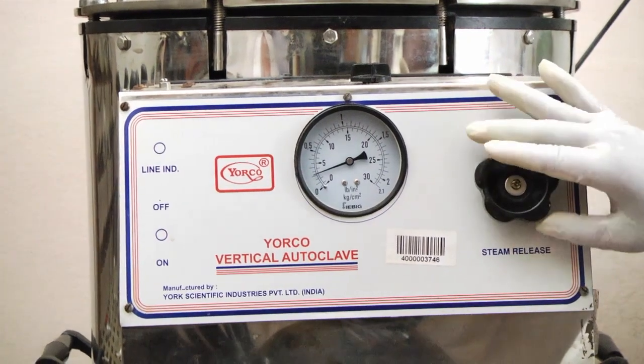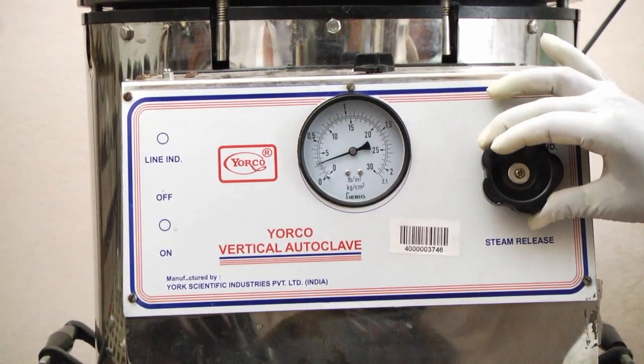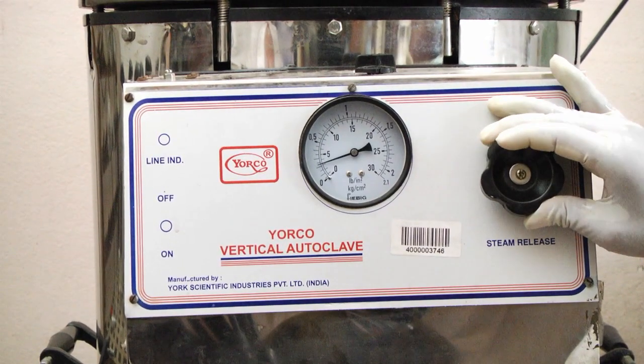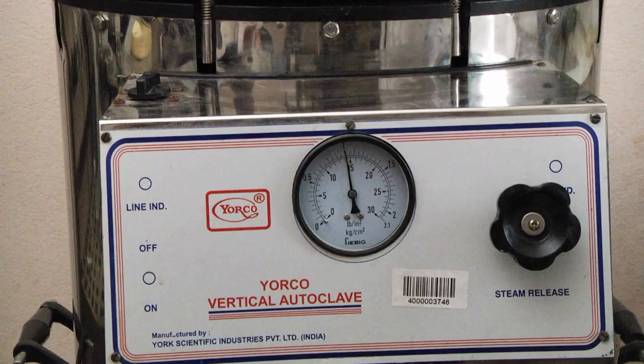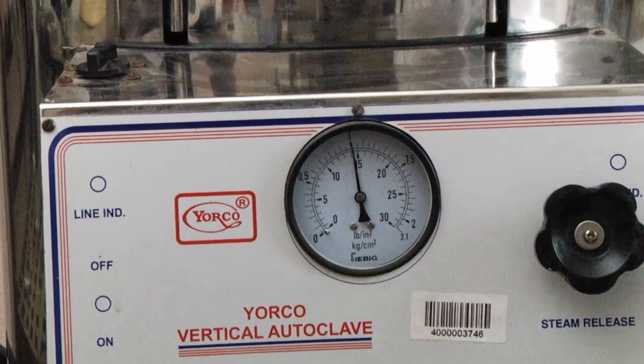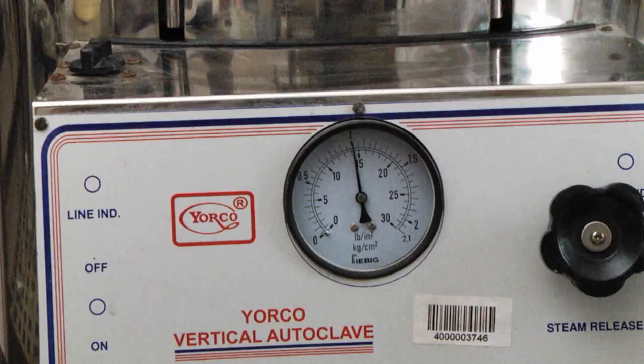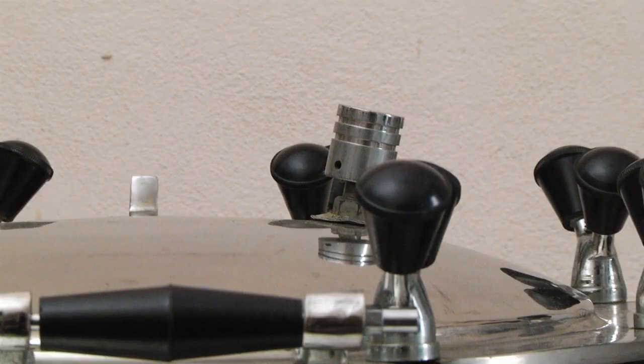Close the air cock. This will cause the pressure to rise and with it the temperature of the saturated steam. When the required pressure has been reached, as shown on the pressure gauge, and the excess steam begins to be released from the safety valve, reduce the heat and begin timing using a timer. The heat should be sufficient to maintain the required pressure for the duration of the sterilizing time.